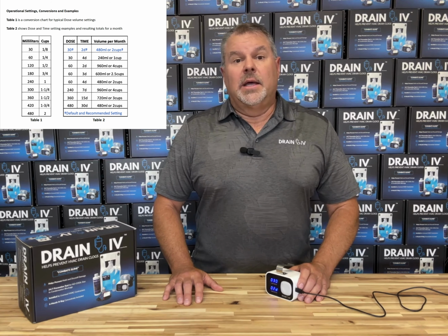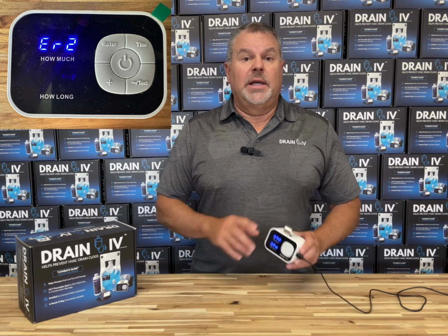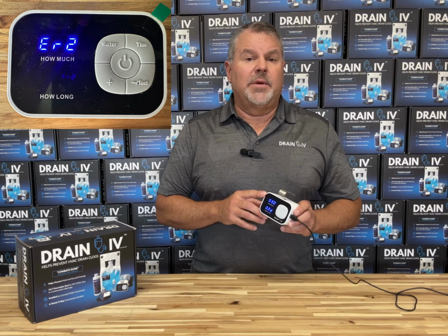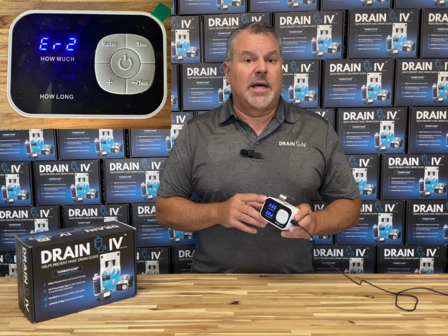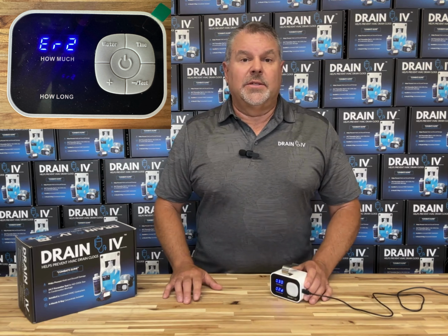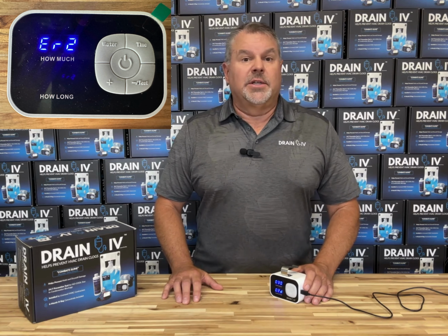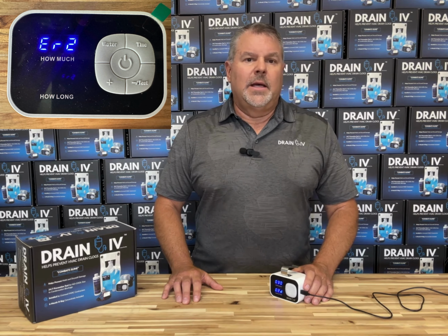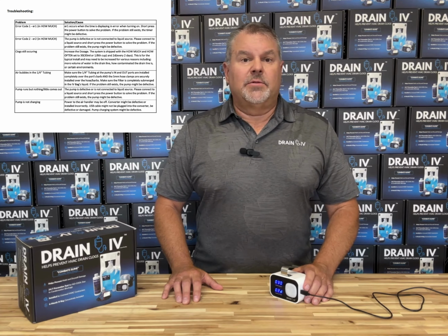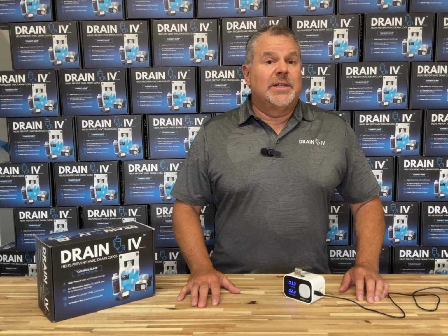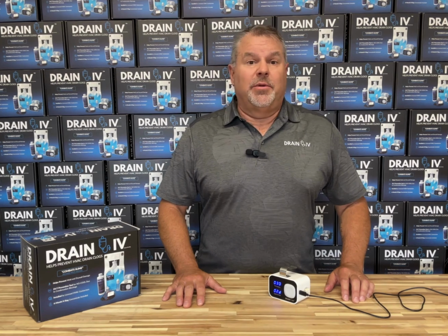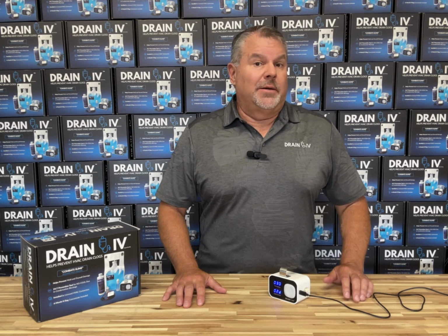If the IV bag goes empty, the pump will show an ER2 error code in the how much display and shut down the pump's timer. To reset the device and clear the error code, single press the power button. If other issues arise, please reference the troubleshooting table in the instructions and contact us if you have any additional concerns. Well, there was a lot here just to find out the pump is already programmed for you and ready to go when powered on.